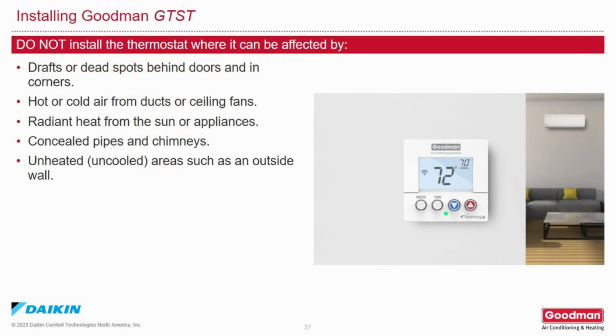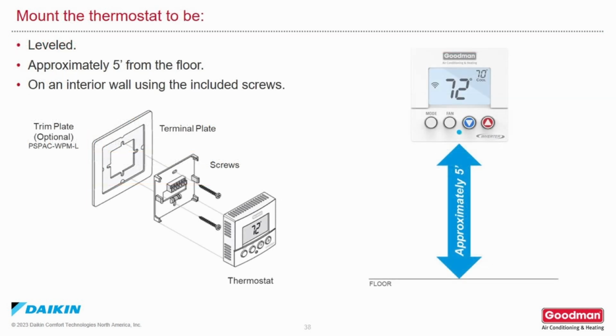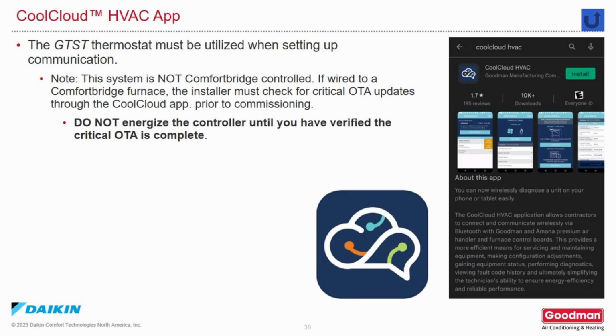Do not install a thermostat where it could be affected by drafts or dead spots behind doors and in corners, hot or cold air from ducts or ceiling fans, radiant heat from the sun or appliances, concealed pipes and chimneys in the wall, or unconditioned areas such as outside walls. Mount the thermostat so it can be leveled, approximately 5 foot from the floor and on an interior wall using the included screws. We're using the CoolCloud HVAC app.